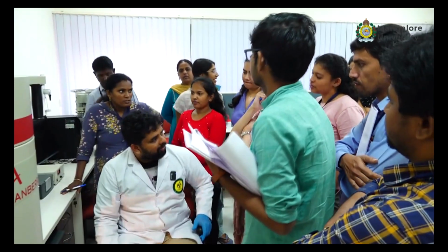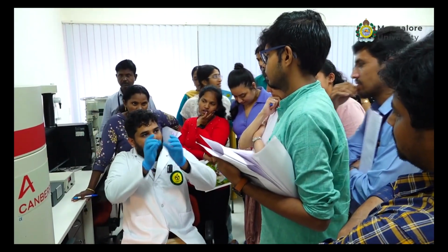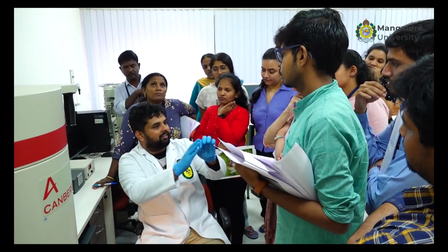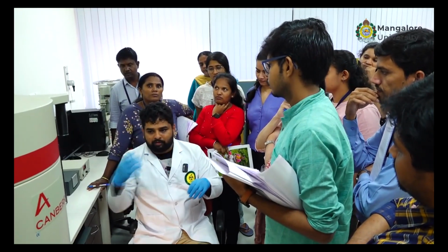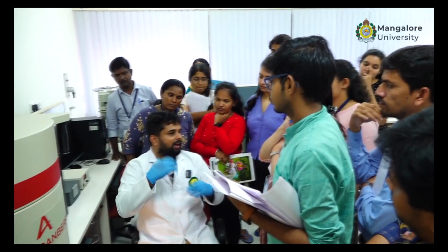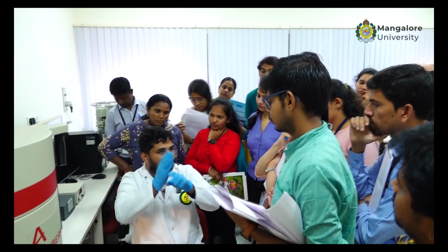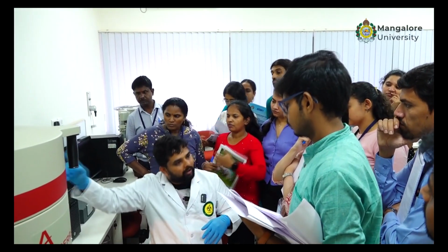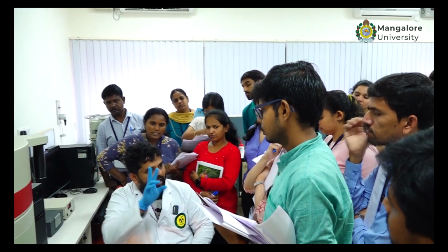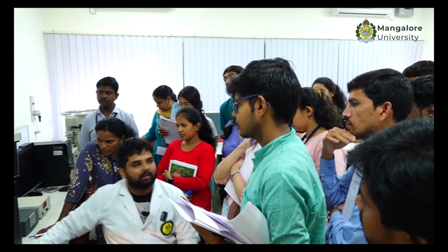Coincidence, it's the same, because we said coincidence peak. So what happens is, as explained in yesterday's class, the signals from the detector are produced in the nanosecond range, whereas the MCA has a microsecond range or something like that. So when you get two gammas, 1173 and 1332, within that time, they add up. So we get one peak, the addition of both. That is what is called a coincidence peak or sum peak. It is over here, 2.505.